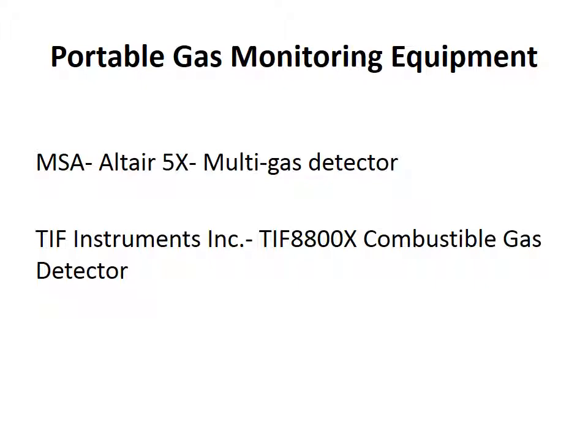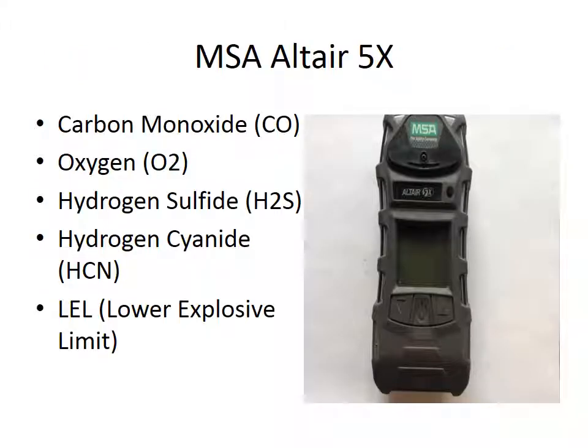The portable gas monitoring equipment that we have at the Wexford Volunteer Fire Company includes an MSA Altair 5X multi-gas detector and a TIF Instruments Incorporated TIF 8800X combustible gas detector. In the next few slides, we're going to review the operation of each piece of equipment so that you can become more familiar with it. The MSA Altair 5X is designed to monitor for carbon monoxide, your oxygen level, whether you're in an oxygen enriched or oxygen deficient environment, hydrogen sulfide, hydrogen cyanide, and what we're going to focus on in this presentation, the lower explosive limit, or the combustible gas level.